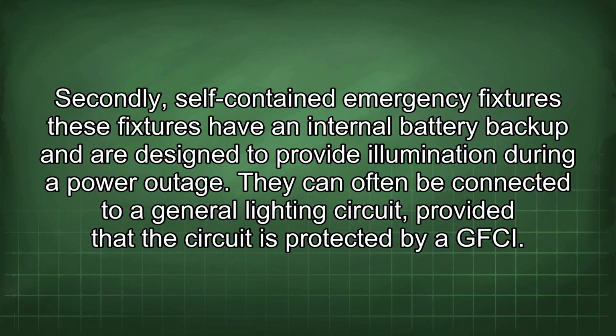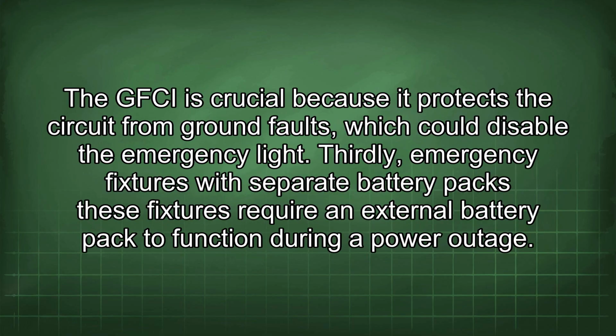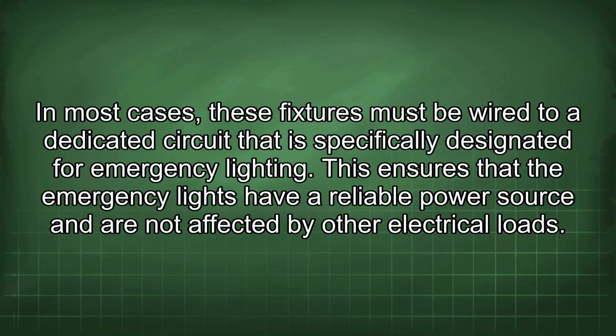Secondly, self-contained emergency fixtures. These fixtures have an internal battery backup and are designed to provide illumination during a power outage. They can often be connected to a general lighting circuit, provided that the circuit is protected by a GFCI. The GFCI is crucial because it protects the circuit from ground faults, which could disable the emergency light. Thirdly, emergency fixtures with separate battery packs. These fixtures require an external battery pack to function during a power outage. In most cases, these fixtures must be wired to a dedicated circuit that is specifically designated for emergency lighting. This ensures that the emergency lights have a reliable power source and are not affected by other electrical loads.